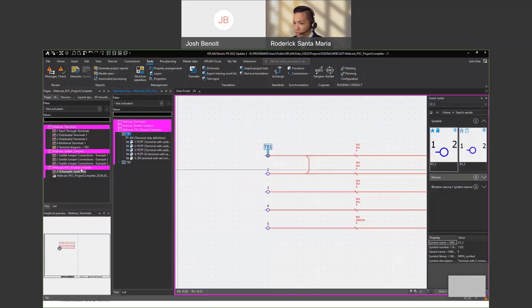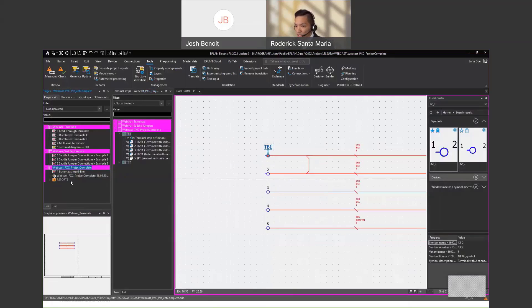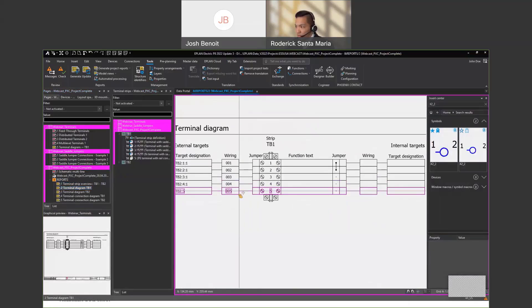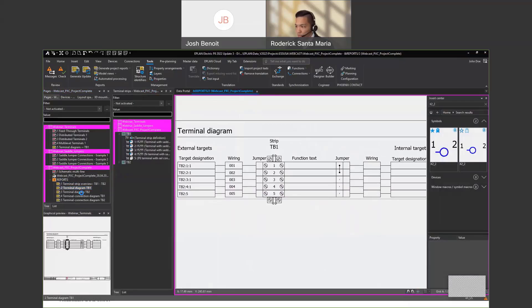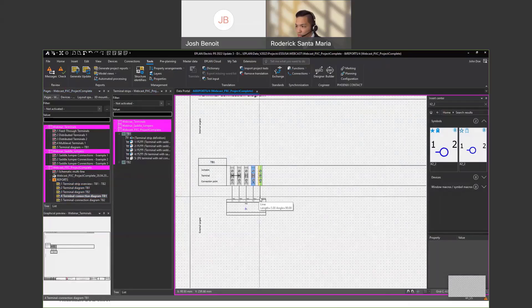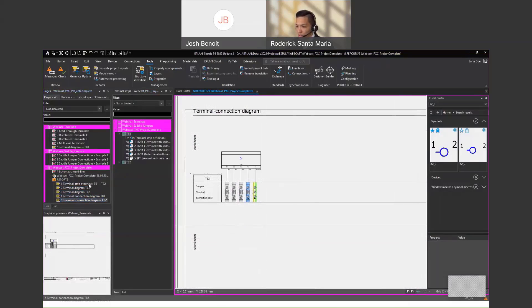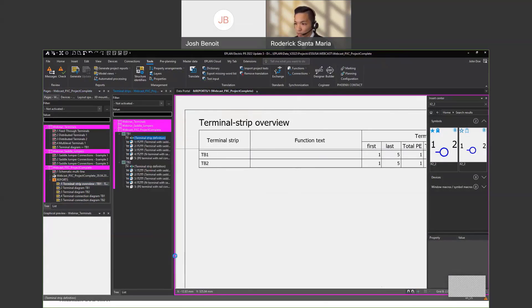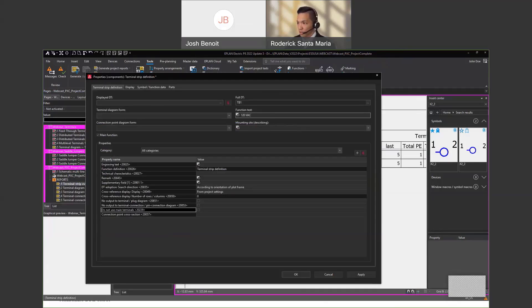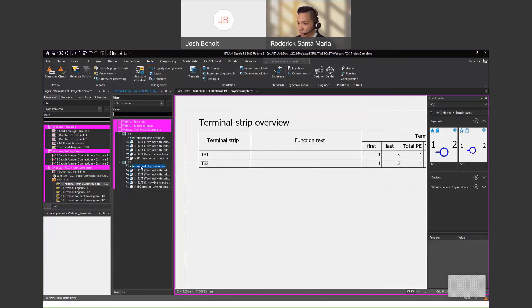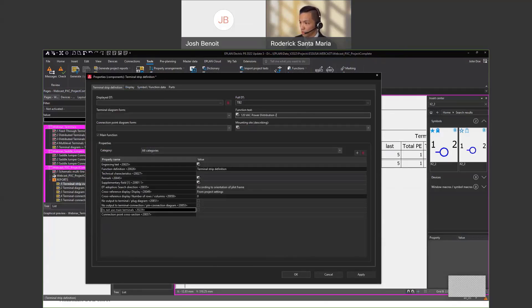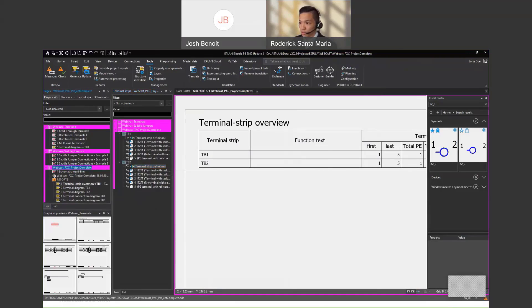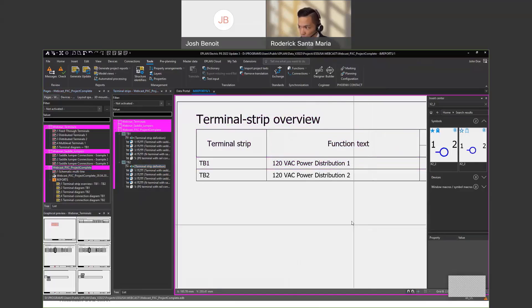In my case, if I were to generate my project reports, I can see my terminal diagrams for TB1, same for TB2, and also a nice terminal connection diagram as well. When it comes to terminal strip definition, those are your markers — you would have to add it within the terminal strip definition property under Function Text. For example, I can copy this for my first terminal and hit OK, same for TB2. If I update my reports, you'll see that it'll get added under my terminal strip overview — that's where it's coming from.